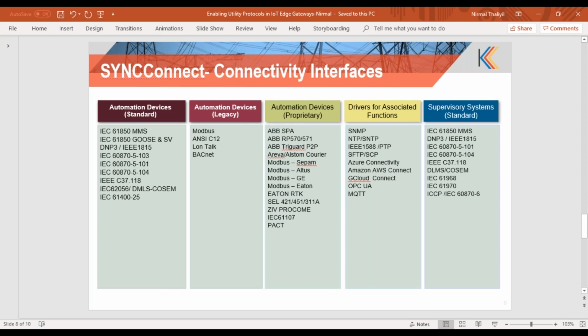SYNCConnect can also be enabled with IEEE C37.118 to connect phasor measurement units out in the field, and it will stream the data to a central phasor data concentrator, or convert the data into legacy protocols to send out to a SCADA system as well. It also supports IEC 62056, the DLMS protocol, for collecting energy meter data, and IEC 61400 is a sub-variant of the 61850 standard for the wind industry.